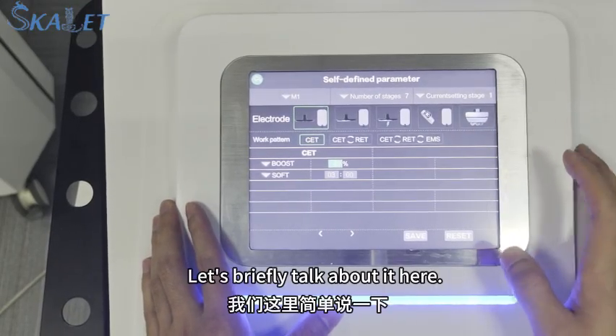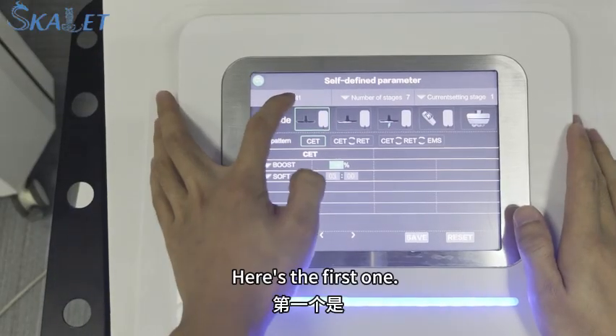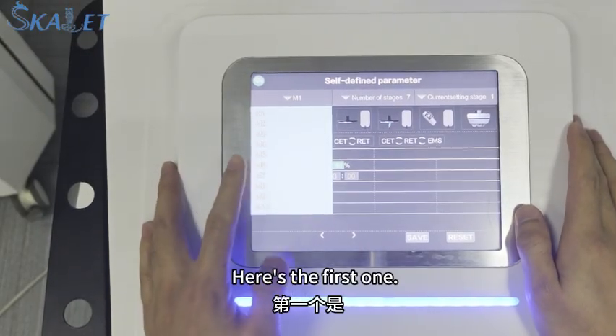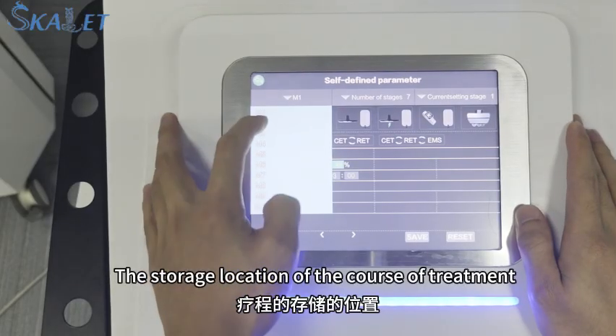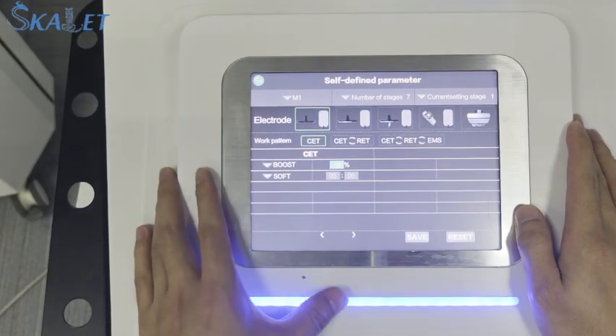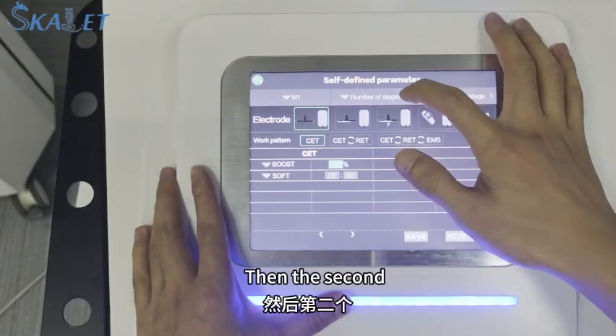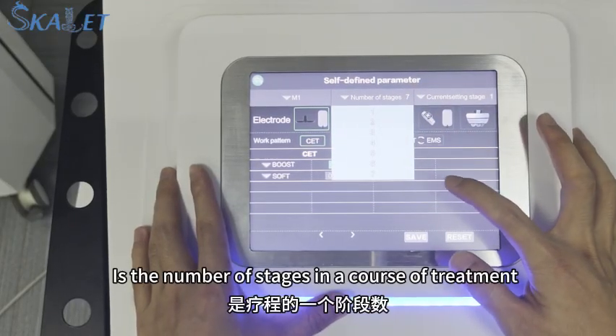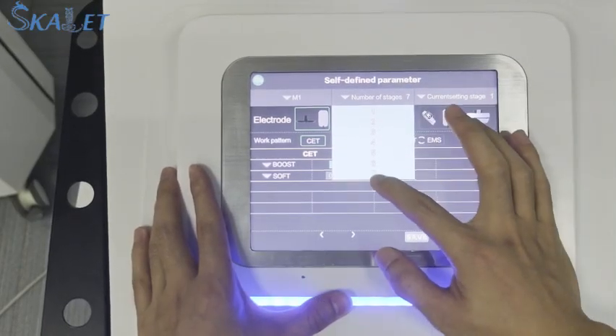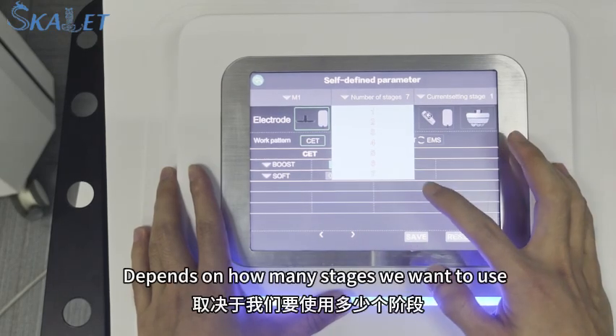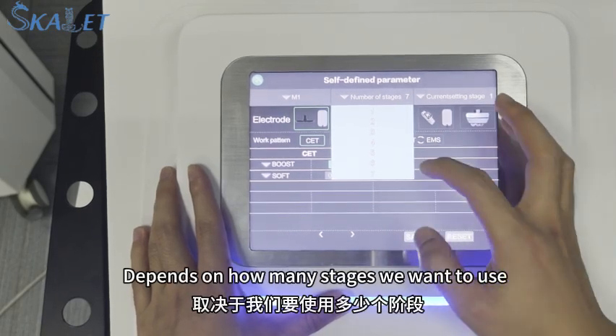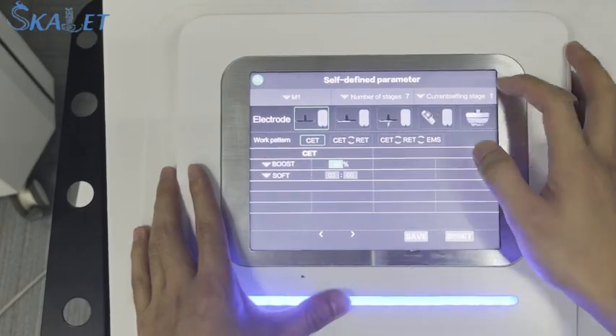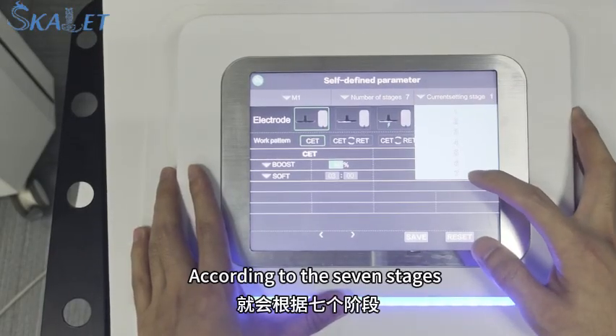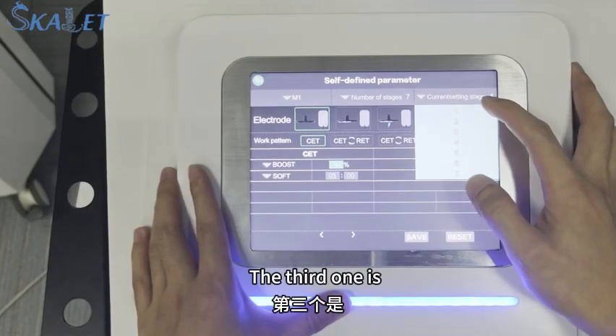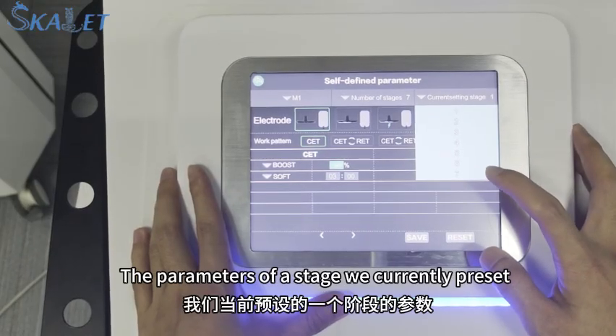Let's briefly talk about it here. Here's the first one. The storage location of the course of treatment. Then the second is the number of stages in a course of treatment. Set this up. Depends on how many stages we want to use. For example, we use 7 stages. According to the 7 stages, for display. The third one is the parameters of a stage we currently preset.